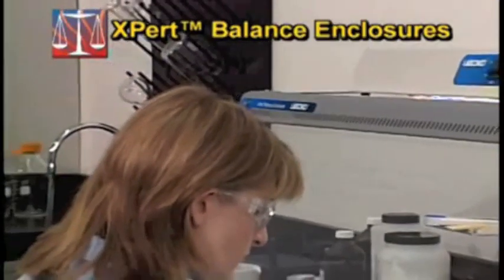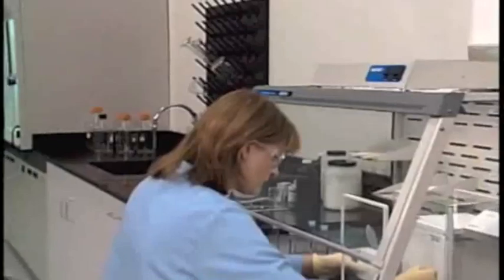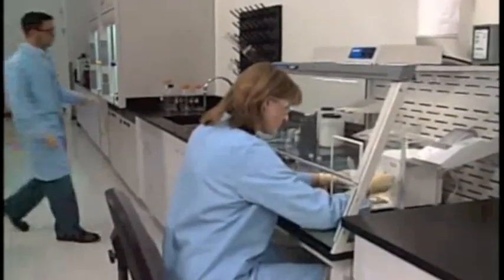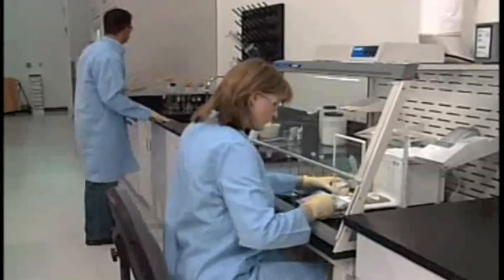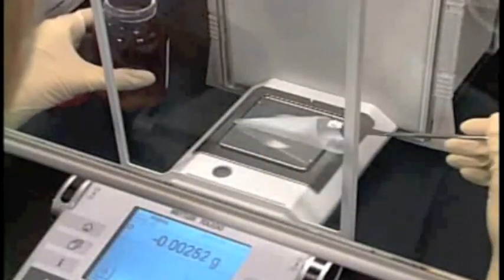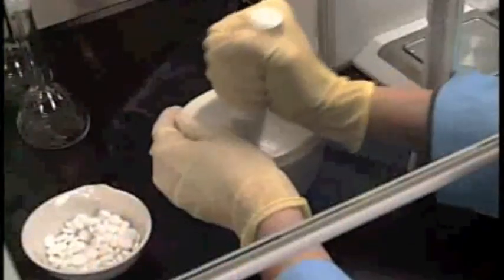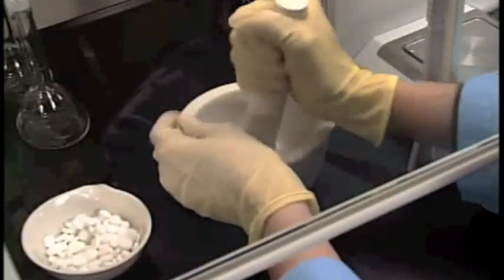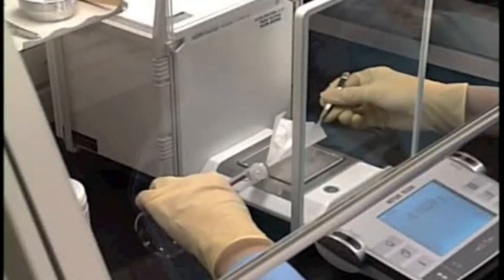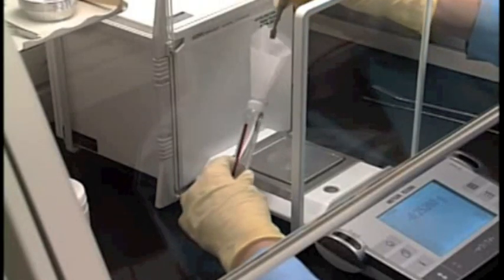The XPert balance enclosure offers maximum containment of toxic powders found in weighing applications while keeping turbulence and airflow that can affect balance performance to a minimum. Pharmaceutical research frequently involves weighing potent drug powders that have the potential to become airborne and enter the operator's breathing zone. These airborne particles may not be visible to the naked eye but may be harmful in minute quantities.